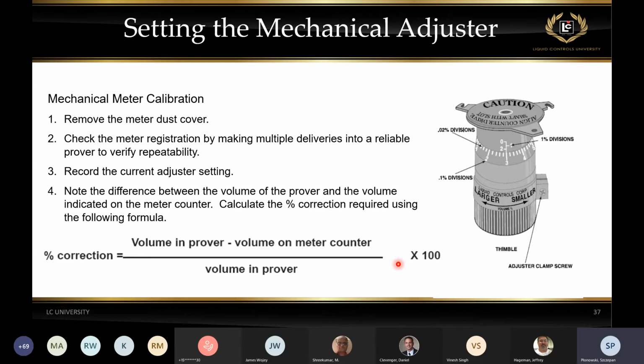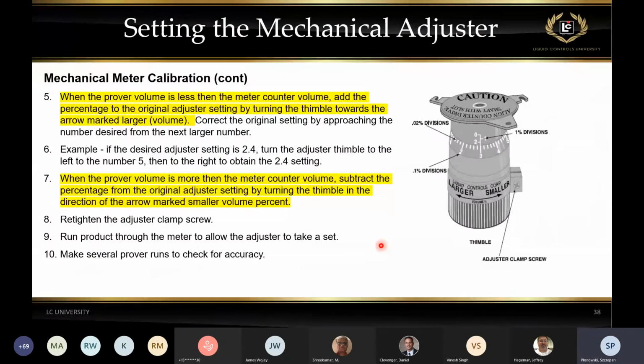The simple formula that allows us to calculate percentage error or percentage of correction is volume in a prover minus volume indicated by the meter, divided by volume in a prover. If we multiply that number by 100, that's going to give us a percentage error. Now, what do we do with that percentage error? Well, it depends. There are really two scenarios.